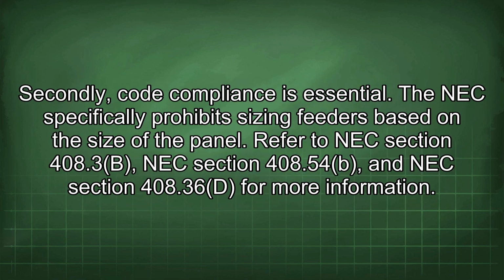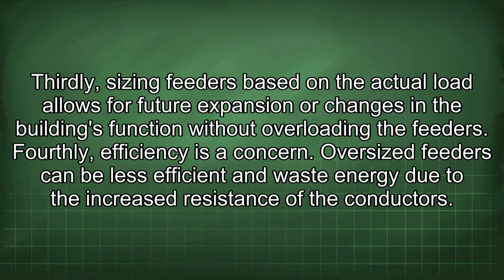Secondly, code compliance is essential. The NEC specifically prohibits sizing feeders based on the size of the panel. Refer to NEC Section 408.3b, NEC Section 408.54, and NEC Section 408.36d for more information. Thirdly, sizing feeders based on the actual load allows for future expansion or changes in the building's function without overloading the feeders. Fourthly, efficiency is a concern. Oversized feeders can be less efficient and waste energy due to the increased resistance of the conductors.